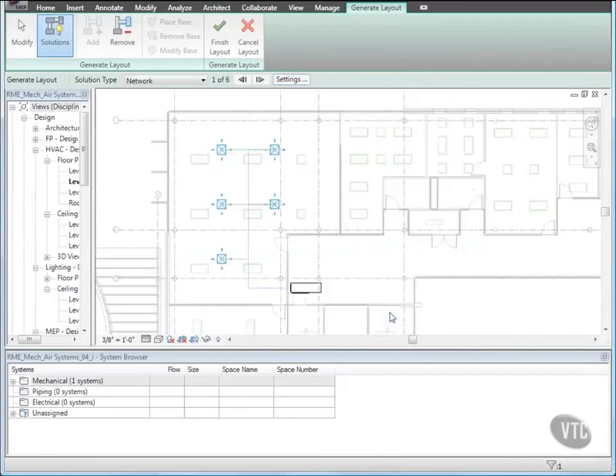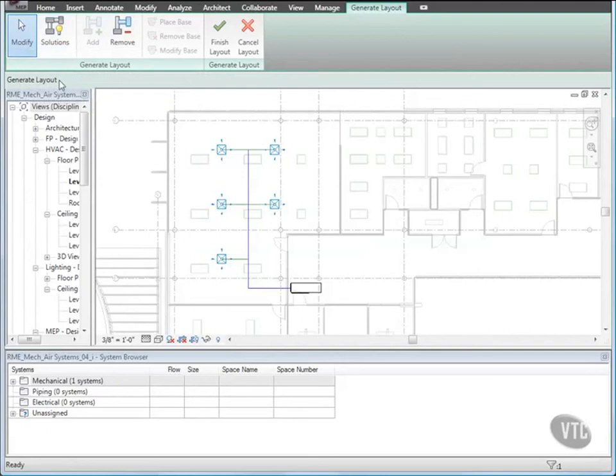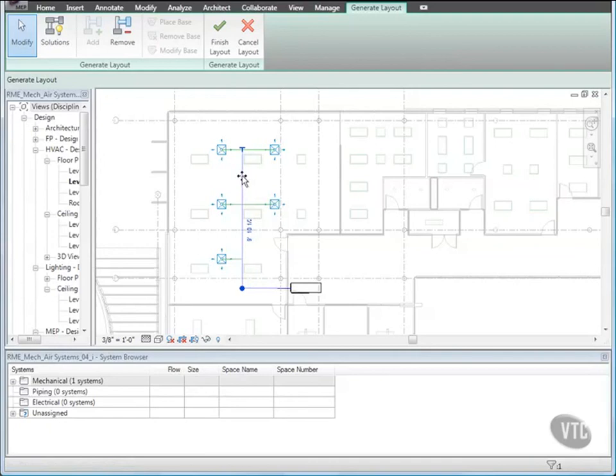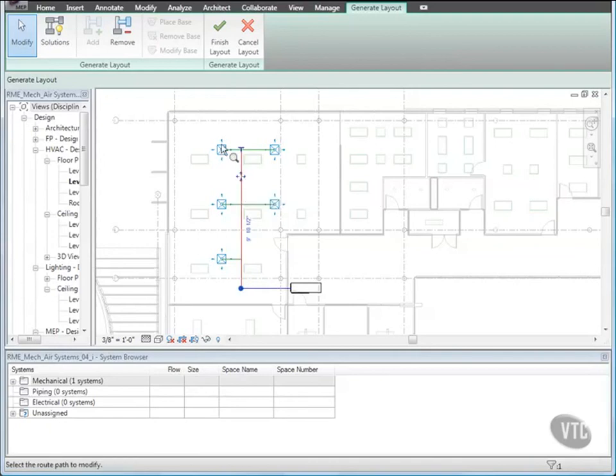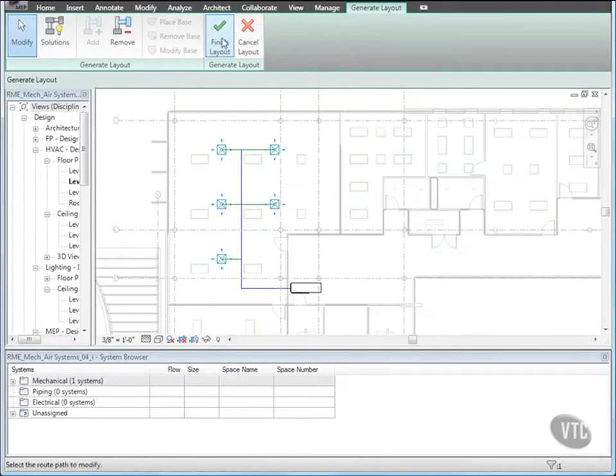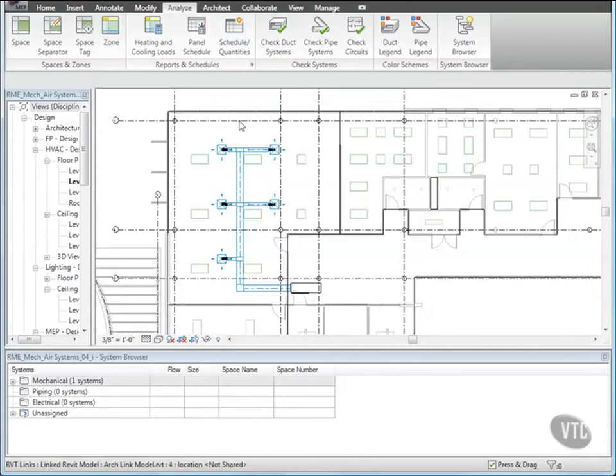Then click Modify and select a vertical segment of the main duct and drag it just to the left of the light fixtures. Be careful not to drag the main duct too close to the diffusers. If there's not enough room for the software to create the necessary fittings, you'll get an error in a later step. Click Finish Layout. Notice that the ductwork is not listed in the system browser because the ductwork is a physical and not a logical connection, and therefore it's not part of the system.